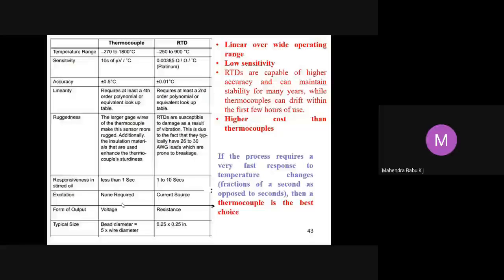And when you compare this RTD with a thermocouple, we have the temperature range. Thermocouple varies from minus 270 to 1800 degrees Celsius, whereas RTDs vary from minus 250 to 900 degrees Celsius. RTDs are linear over wide operating ranges and have low sensitivity. RTDs are capable of higher accuracy and can maintain stability for many years, while the thermocouple can drift within the first few hours of use. And regarding cost, RTDs are higher cost than thermocouple. If the process requires a very fast response to temperature changes, then a thermocouple is the best choice, because the response is less than 1 second here, whereas for RTDs it is 1 to 10 seconds. The response is very slow when you use RTDs. Where a fast response is required, the thermocouples are the best.